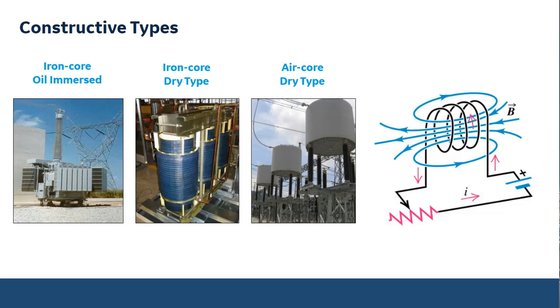Very robust technology. There are no parts to fail. Very light design compared to the other ones. And of course, if the design is light and simple, we can only expect that the cost will be much more competitive than the other solutions. Another main advantage of air core dry type compared to the oil immersed technology is the presence or absence of oil. If the air core dry type doesn't have oil, that's excellent for the environment, so there's no leakage risk. And of course, there is no risk of explosion and fire. There are more advantages which I'm going to mention during the presentation.